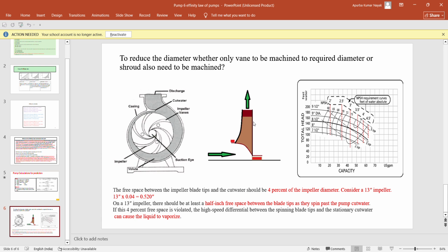It is better you do a combination: some diameter change as well as RPM change. So drastic diameter change or RPM change is not required. So head requirement will also be slightly less, because you are increasing or decreasing the diameter slightly and RPM slightly. So your final head will be slightly less than if you choose only RPM or only diameter. Then you see the graph.